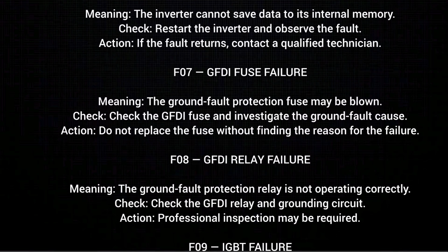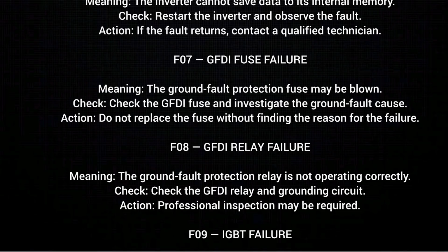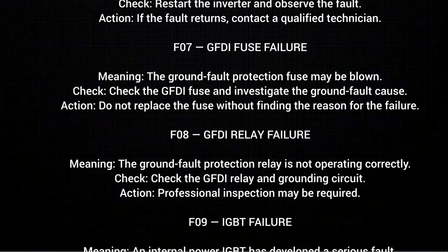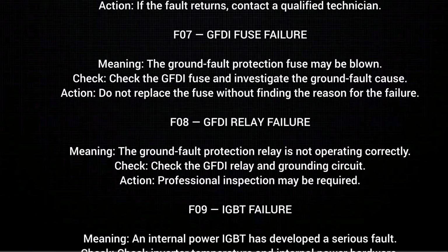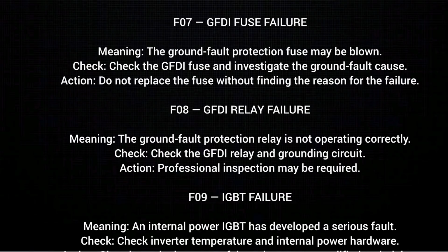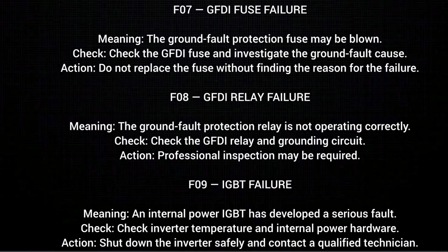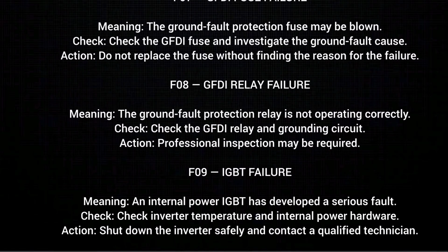F07 GFDI fuse failure, meaning the ground fault protection fuse may be blown. Check. Check the GFDI fuse and investigate the ground fault cause. Action. Do not replace the fuse without finding the reason for the failure.